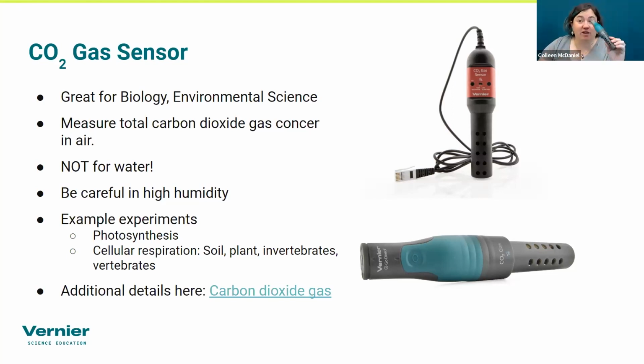The great thing about the carbon dioxide gas sensor is that it doesn't necessarily have degradation to it, so it can last a really long time. There is a lamp inside of it, and that's how it's measuring the CO2 in the air. That lamp will eventually go out, but I have seen CO2 sensors last upwards of 12 years, so it's going to be a while before that sensor dies on you.